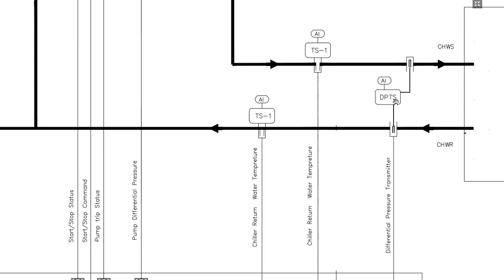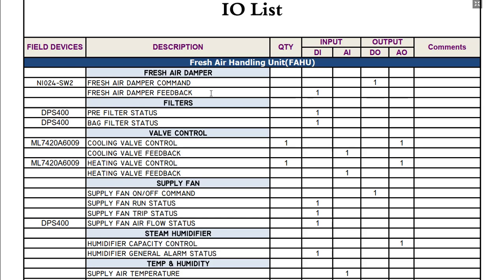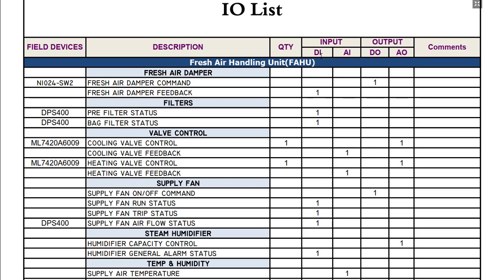That's all for the schematic diagrams. Now we will discuss the IO list for all these equipment. The IO list provides the following information: field devices with model numbers, description of the point, quantity of field devices, DI points, AI points, DO points, AO points, and a comments section. I have made this IO list for the fresh air handling unit we just discussed. This is an actual IO list based on Honeywell products, so all the model numbers shown are from Honeywell.